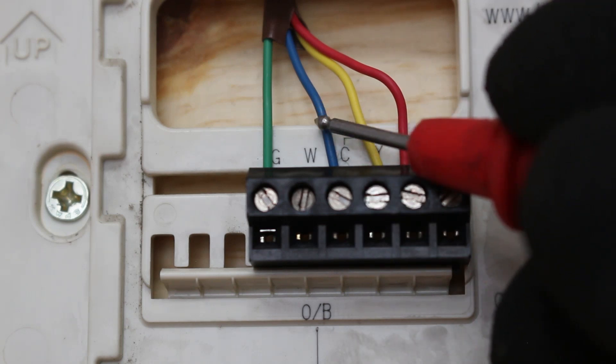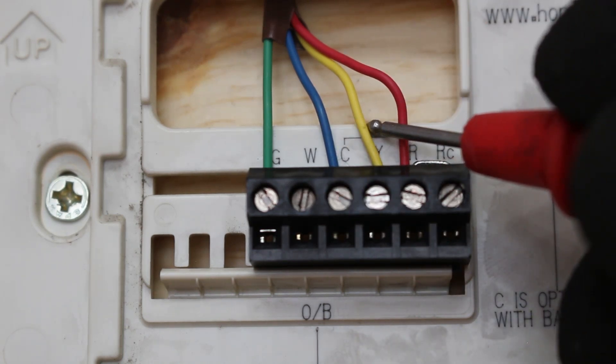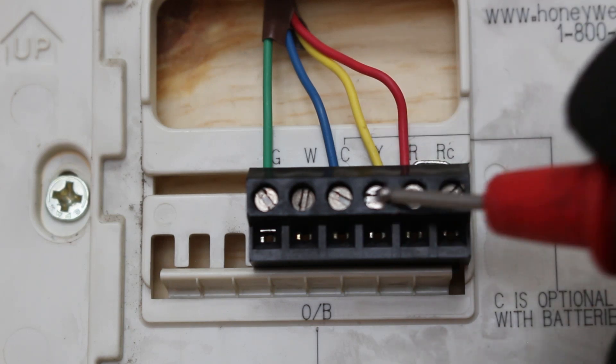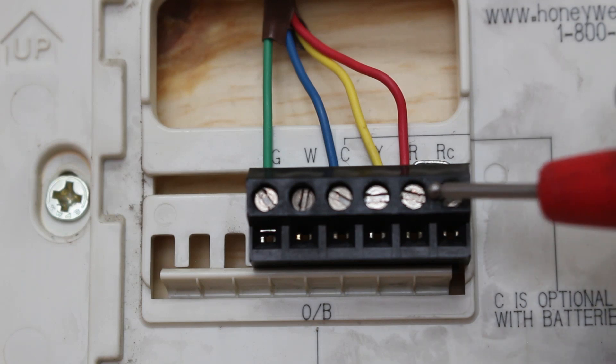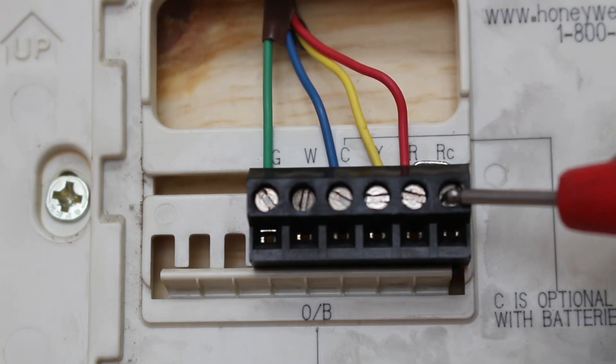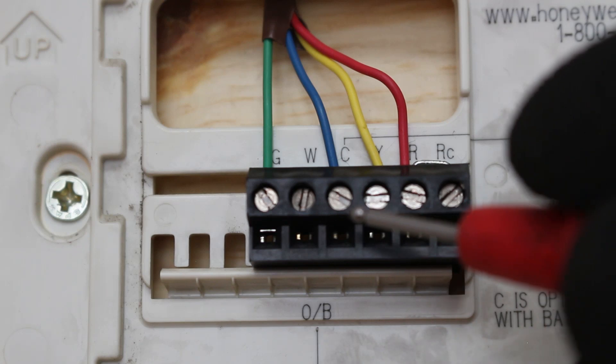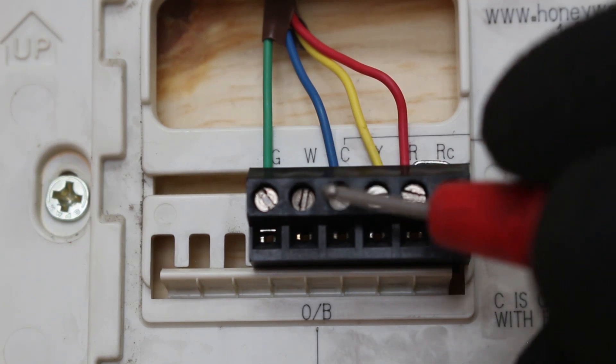Next you can see we have a blue wire which is our common. Y is our cooling in yellow. Then we have R which is jumped over to RC. So these two terminals is our power in, so 24 volts and common. So that's how we complete the circuit.